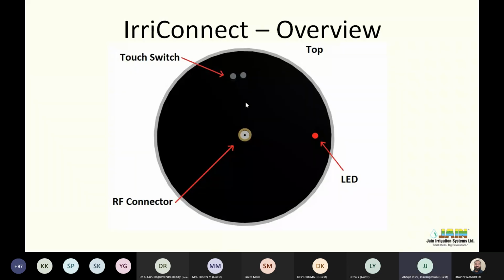It has got a touch-sensitive switch. So during troubleshooting, the person has to go there, touch his hand - capacitive sensors are there - and then he can get connected or paired with his mobile. The Bluetooth will be activated, because you cannot keep the Bluetooth continuously on since there is no separate power available. Then the LED will start blinking so you know the RTU is now communicating with the Bluetooth app, and there is an RF connector inside.